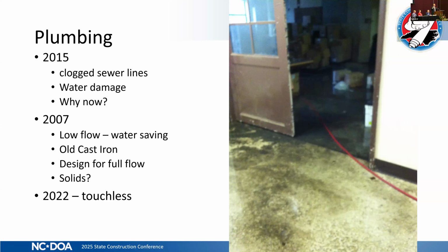And they could hear this rock move through the lines as they continued to jet massive amounts of water to move that thing. It hit the vertical riser and they could hear it scraping the sides and breaking more stuff free as it moved. Apparently there were more clogs on the lower level of this building because when that clog hit the basement of our building, a pressure wave was created, and that pressure wave made the downstairs toilets throw up.